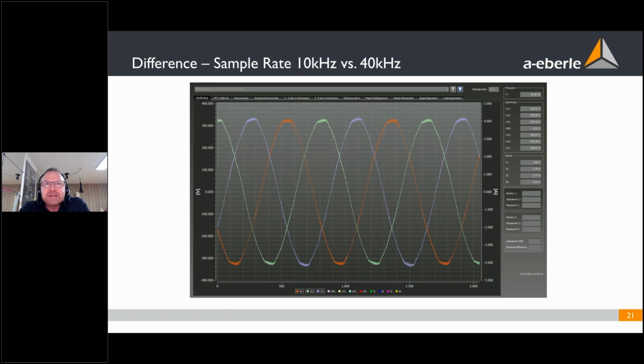If I do the same snapshot at the same coupling point with the PQ-Box 200, we now see the high frequency which happened in this network. This is 10 kilohertz with 1.7 volt. So if the interference in this grid were 22 kilohertz, it could be a high disturbance. So the PQ-Box 200 also can see those disturbances.